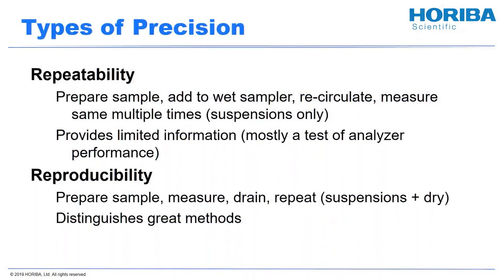A little more on types of precision. For repeatability: if I prepare a sample and I have a liquid system that lets me recirculate, I add it to my laser diffraction analyzer, recirculate, and hit measure multiple times. You should have the same result multiple times in a row. That's very reassuring and an important step, but it does provide limited information — it tells you about your analyzer performance and whether your suspension will be stable in the instrument for a few minutes. Once you get through repeatability, the next question is reproducibility. You take a bucket of material, prepare a sample, measure it, drain the system, and repeat everything from the beginning with fresh liquid, fresh dispersant, and another lot of sample from your bucket. Reproducibility — getting the same answer time after time from a bucket of material — is really what distinguishes a great method.